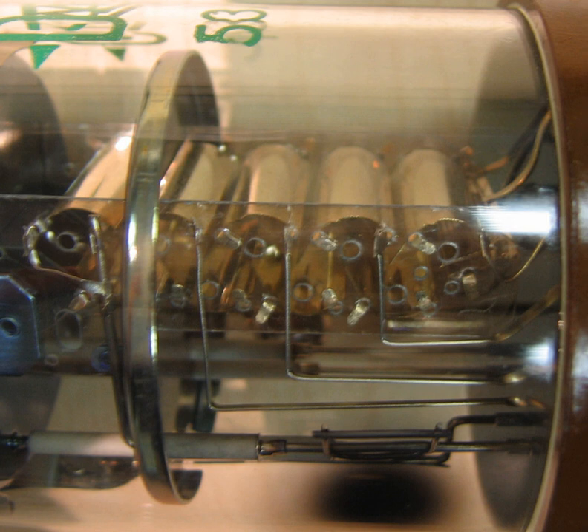Structure and operating principles: Photomultipliers are typically constructed with an evacuated glass housing using an extremely tight and durable glass-to-metal seal like other vacuum tubes, containing a photocathode, several dynodes, and an anode. Incident photons strike the photocathode material, which is usually a thin vapor deposited conducting layer on the inside of the entry window of the device.